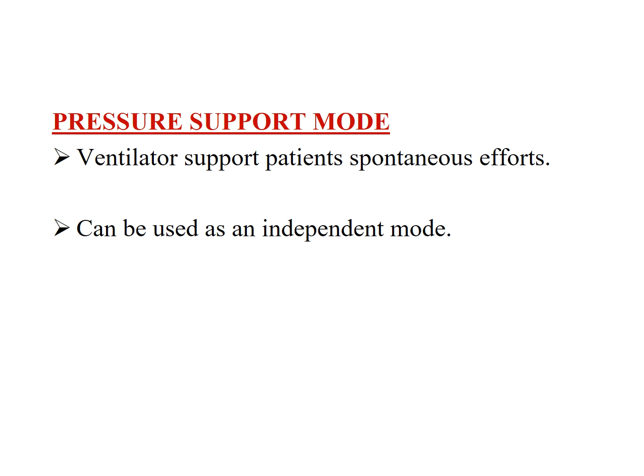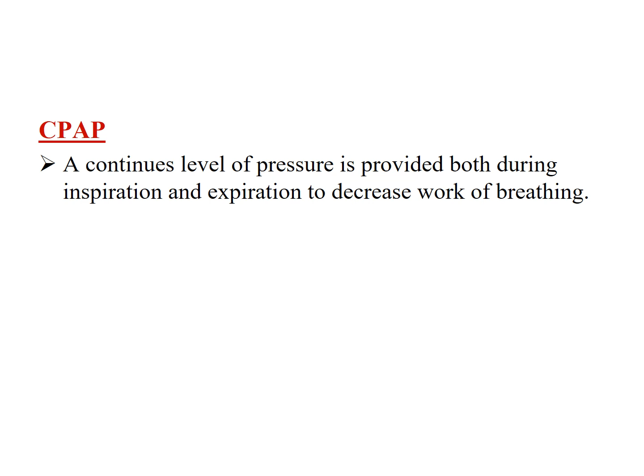Now CPAP is virtually the same as PEEP. CPAP stands for continuous positive airway pressure, which we use interchangeably with positive end expiratory pressure. It's a continuous level of pressure that is provided both during inspiration and expiration, and it would tend to keep alveoli a little distended, hence it would decrease the work of breathing. Just imagine inflating a balloon. If you start inflating a balloon from the beginning, it generally takes a little more effort to begin with. Once a little amount of the balloon is inflated, the amount of effort or pressure required to inflate the rest of the balloon actually decreases. So the same is with the alveoli. If the alveoli are a little inflated because of a continuous level of pressure as a baseline, it would be easier for them to be inflated with the peak inspiratory pressure. Hence, it would decrease the work of breathing.